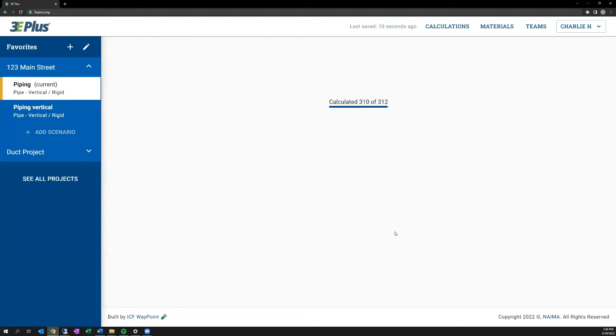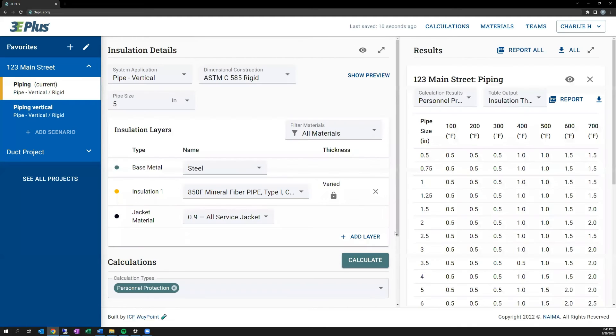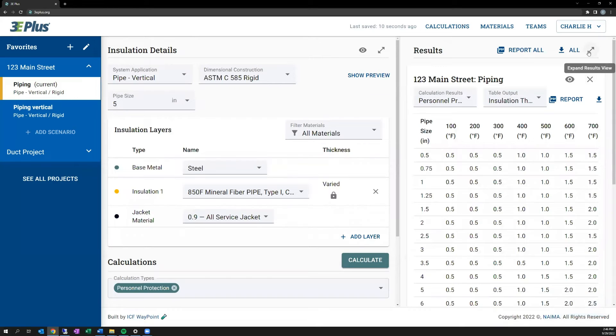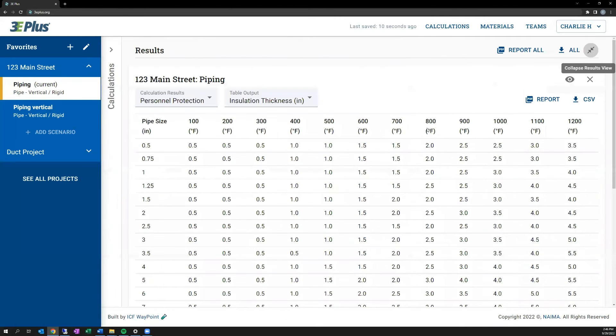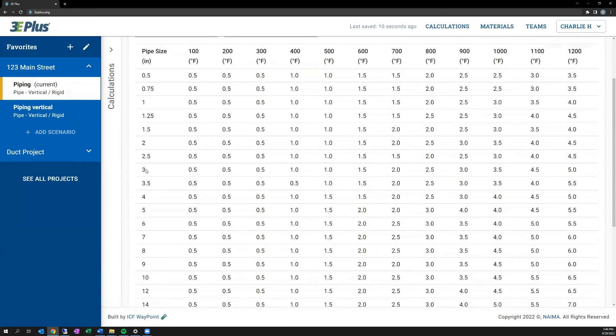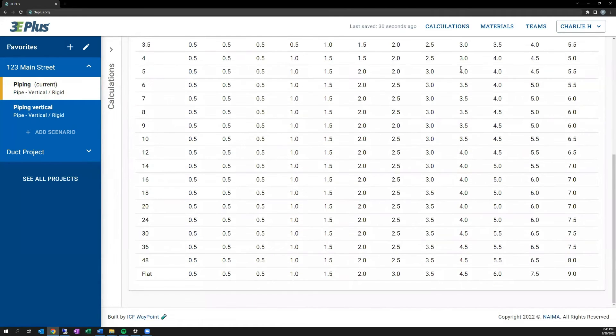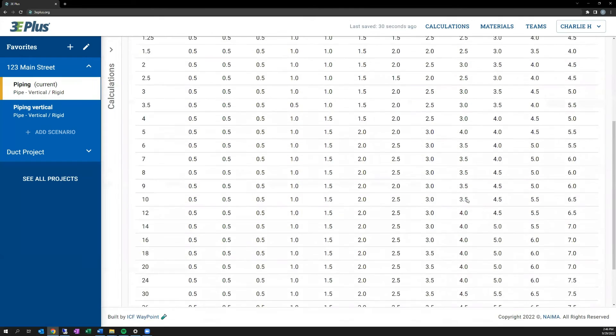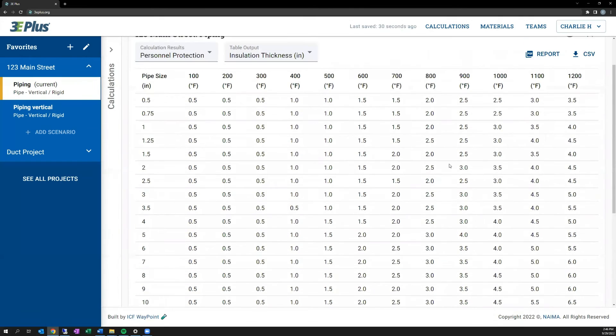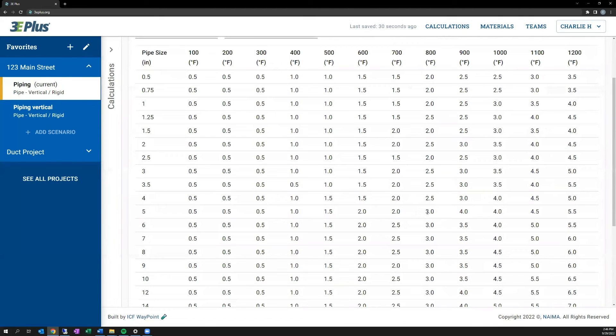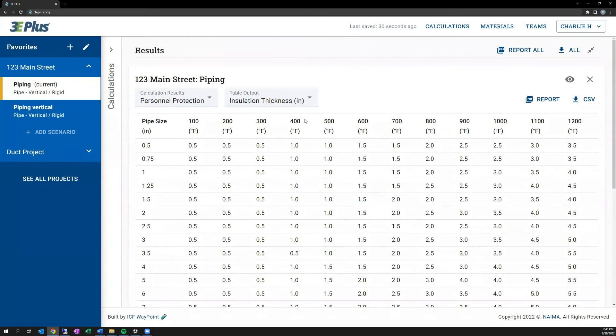And you can see that when the table is created here, and I'll enlarge it, across the top, it has the range of temperatures. Across the side, it has the range of pipe sizes. And within the chart, it tells you the thickness of insulation that's required to meet the personnel protection goal.